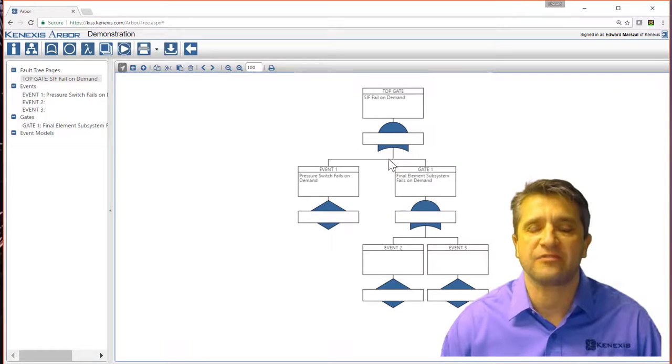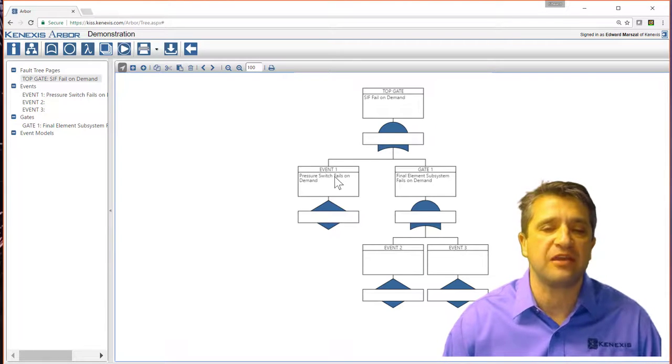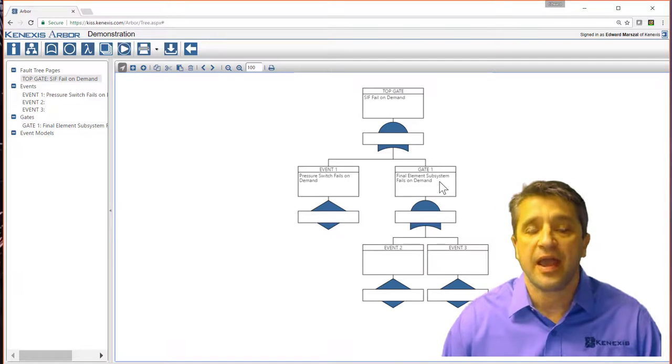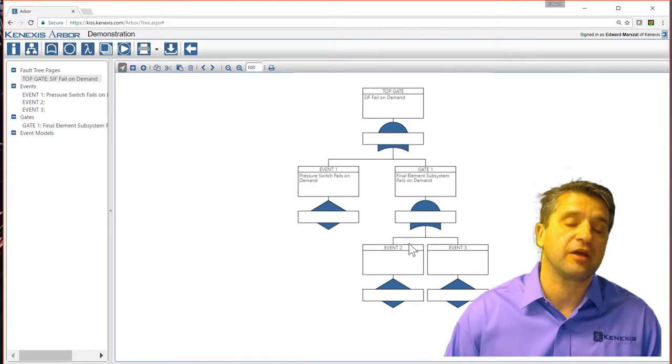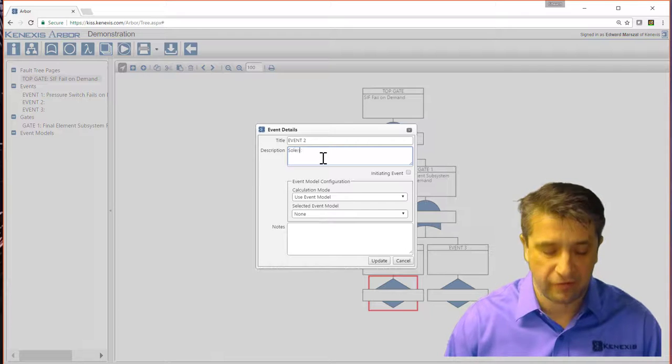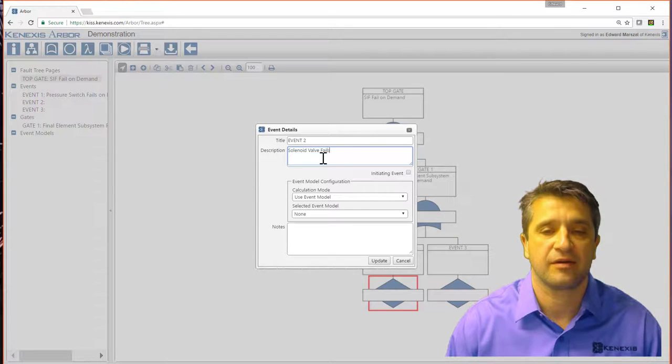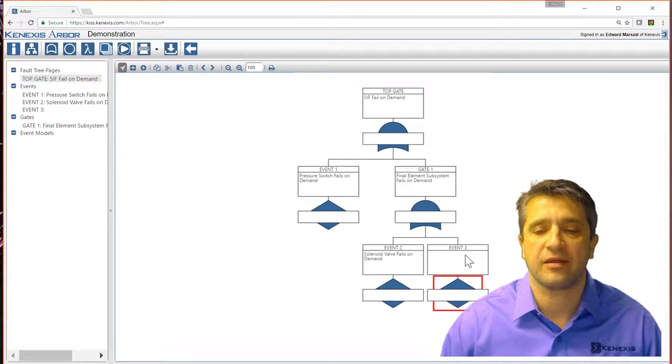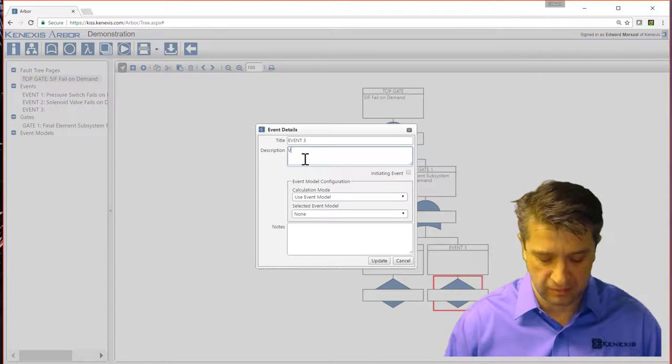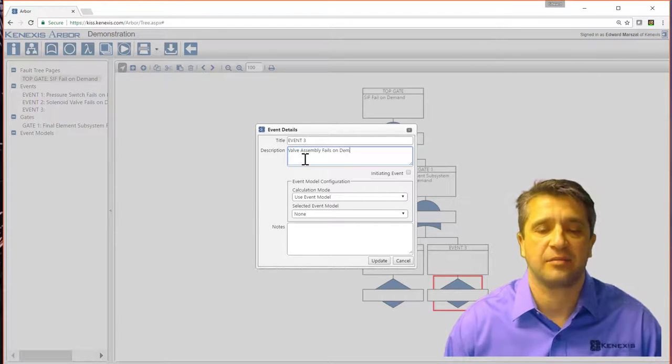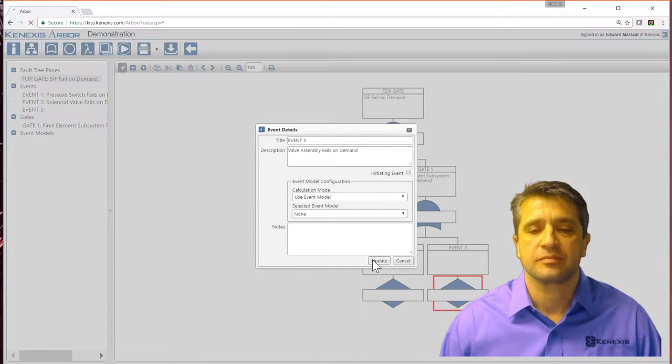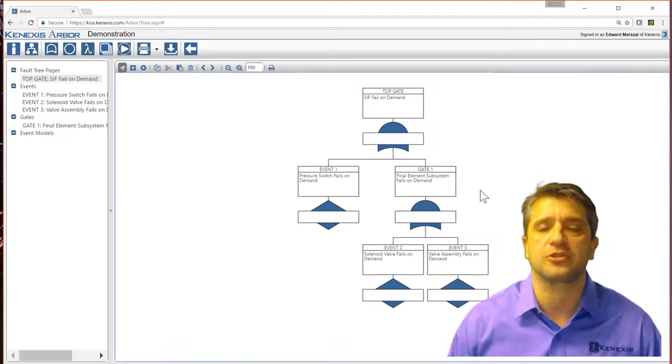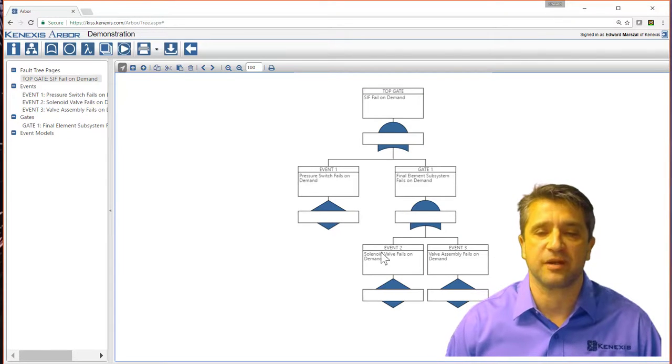The way I've set up the logic, the SIF will fail if either the pressure switch fails or the final element subsystem fails. And the final element subsystem will fail if either the solenoid valve fails on demand or the valve assembly fails on demand. So with that, I've basically set up the general structure of the safety instrumented function.